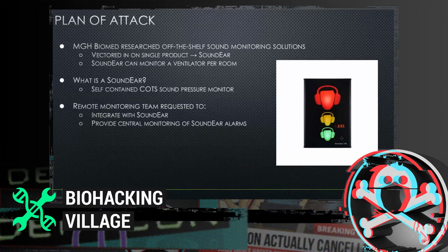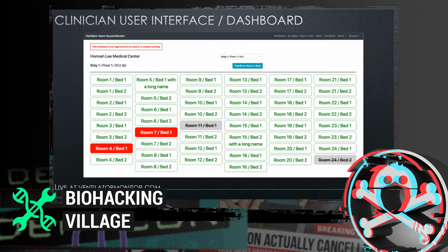So what's our plan of attack? MGH Biomed, for example, researched off-the-shelf sound monitoring solutions. They vectored in on one product, the SoundEar. The SoundEar can deploy a one-to-one system per patient room per ventilator. It's a self-contained consumer off-the-shelf system that can monitor sound pressure. So you can hook a SoundEar with a microphone up to the speaker on the ventilator that auditorily alerts the alarm. And then when the sound pressure is exceeded, when that alarm goes off, the SoundEar can then trip. So we were then requested to integrate with this SoundEar and provide a central means for monitoring the SoundEar and be able to create a central dashboard for when it trips. And now I'm going to pass it over to Sam to go into the architecture.